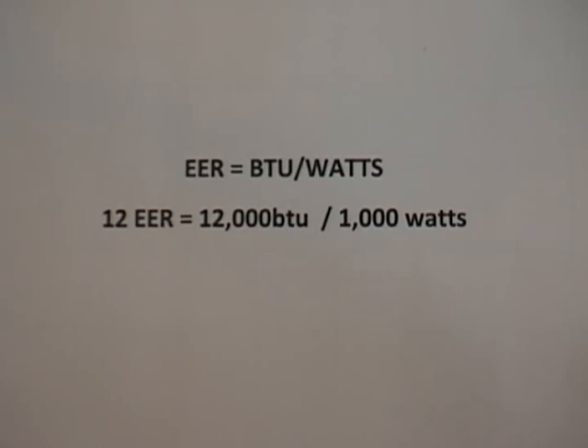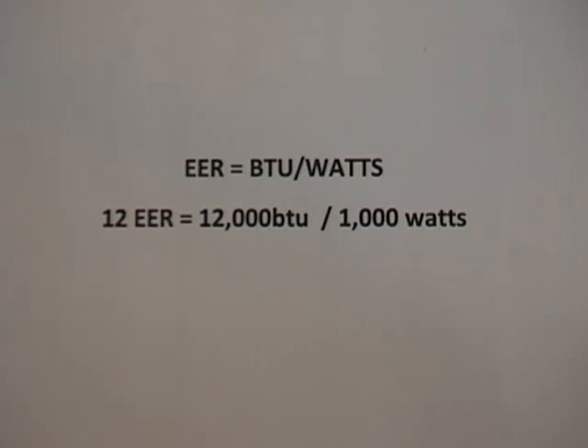Once we've calculated the capacity for the unit, we can divide by 12,000 to get tons of cooling. To get the EER, it's simply BTUs divided by watts — so a 12 EER example would be 12,000 BTUs divided by 1,000 watts, giving a 12 EER. That gives you the real-time capacity of the unit and the real-time EER, which you then compare with the nameplate data to make your corrections and get a more efficient system.